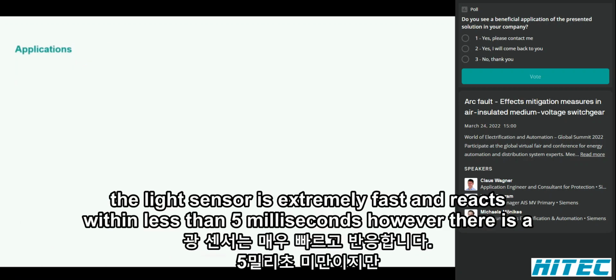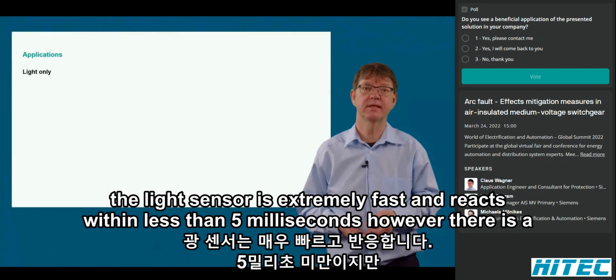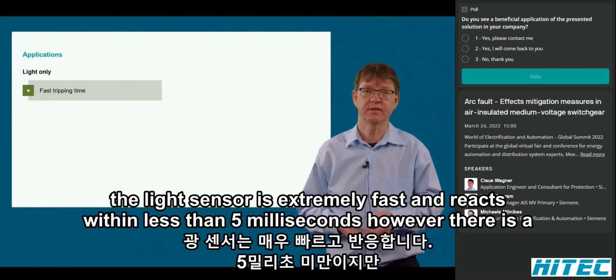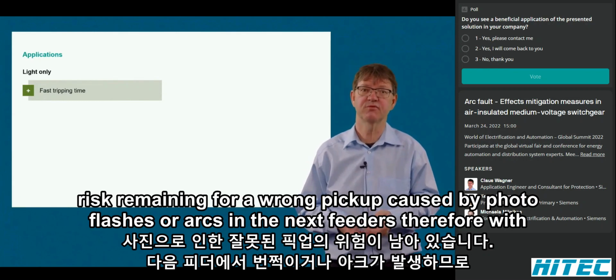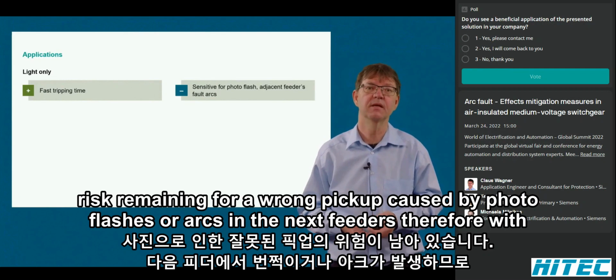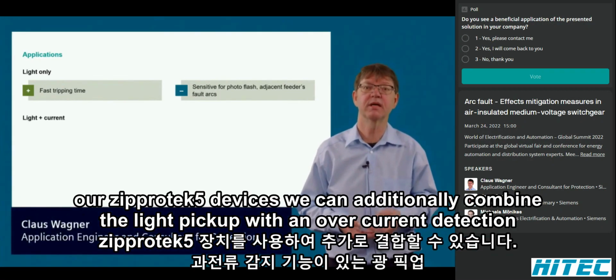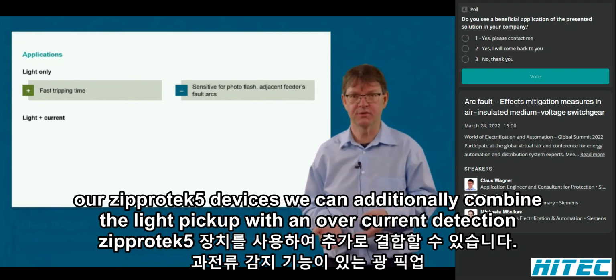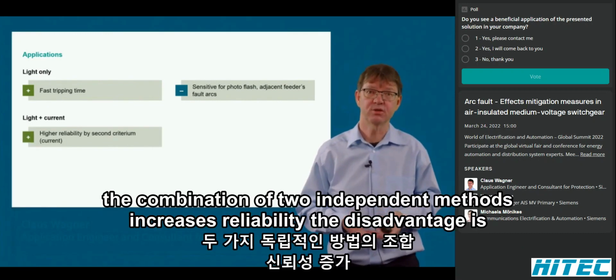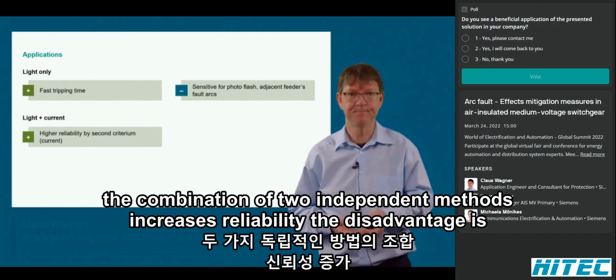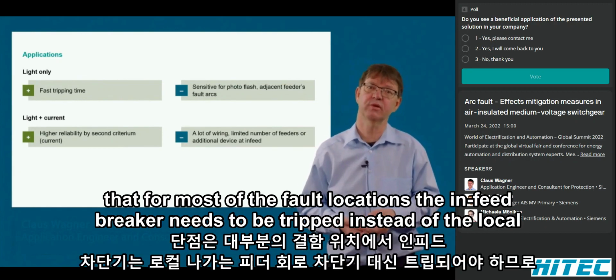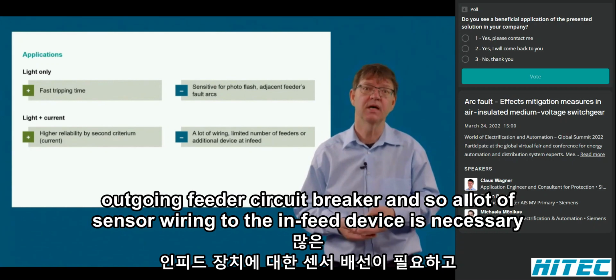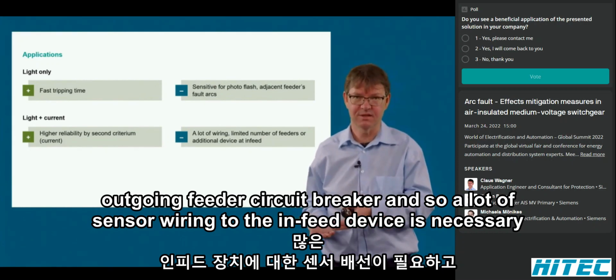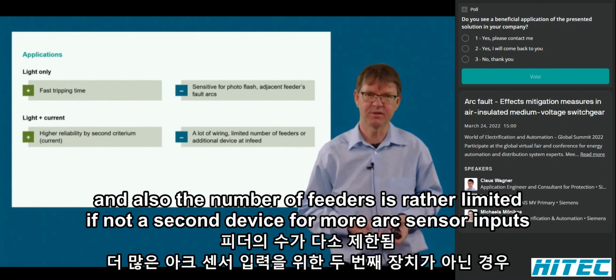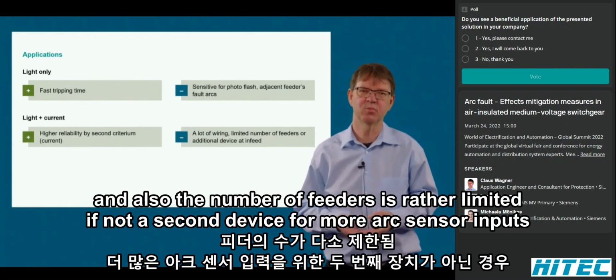The light sensor is extremely fast and reacts within less than 5 milliseconds. However, there's a risk remaining for wrong pickup caused by photo flashes or arcs in the next feeders. Therefore, with our SIPROTEC5 devices, we can additionally combine the light pickup with an overcurrent detection. The combination of 2 independent methods increases reliability. The disadvantage is that for most of the fault locations, the in-feed breaker needs to be tripped instead of the local outgoing feeder circuit breaker, and so a lot of sensor wiring to the in-feed device is necessary, and also the number of feeders is rather limited, if not a second device for more arc sensor inputs is placed at the in-feed.